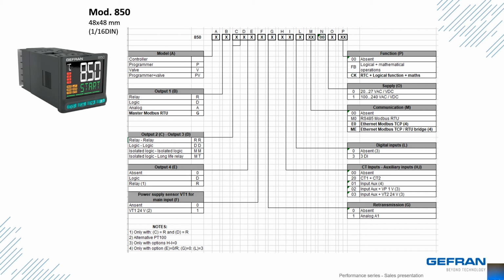On the far right column, M is a note for the Ethernet options. Selecting ME gives you Ethernet, but also the bridge. Under function P, on the far right-hand side, that's where the logic, math, and the RTC, meaning real-time clock, are. So when you're specifying that, it's very easy to order and specify, and a very powerful controller in a 16 DIN package.